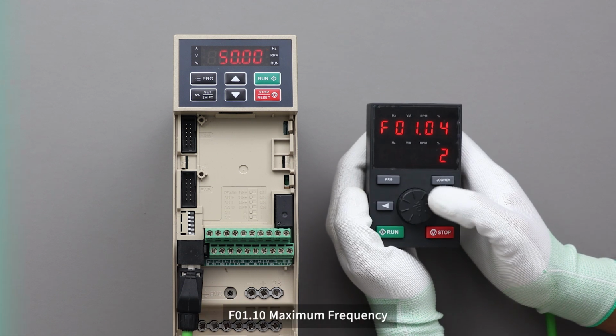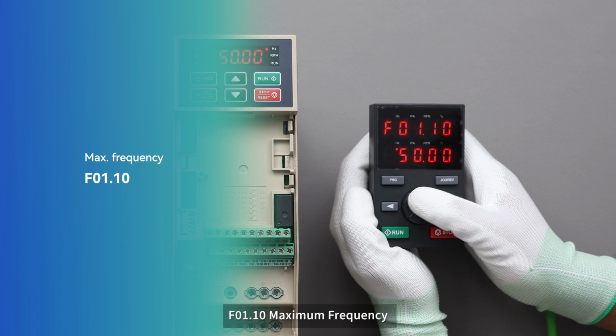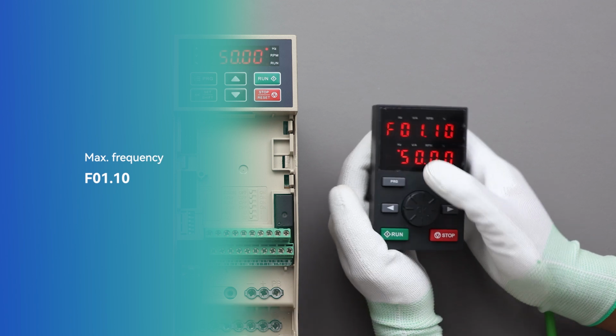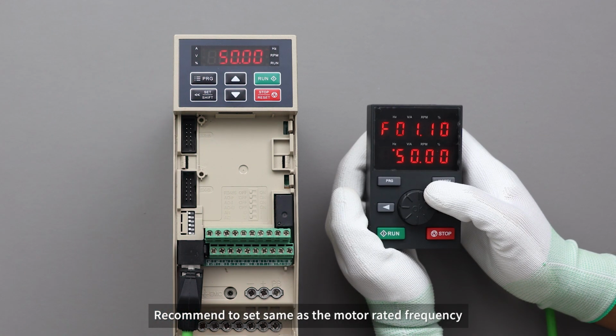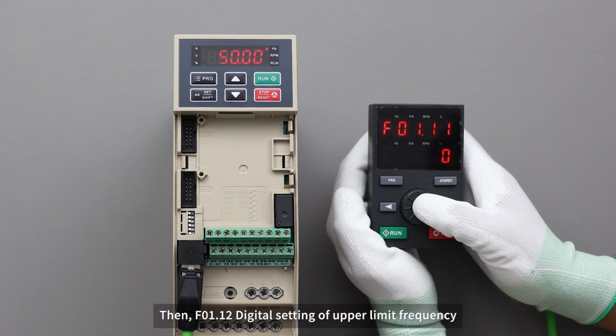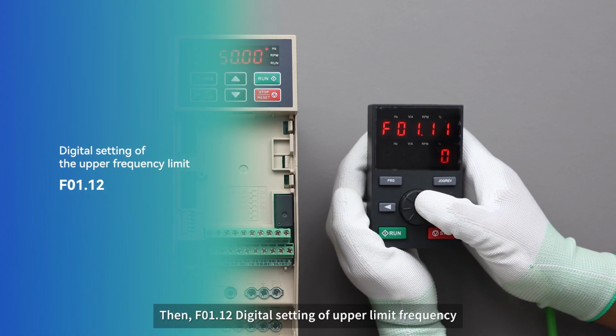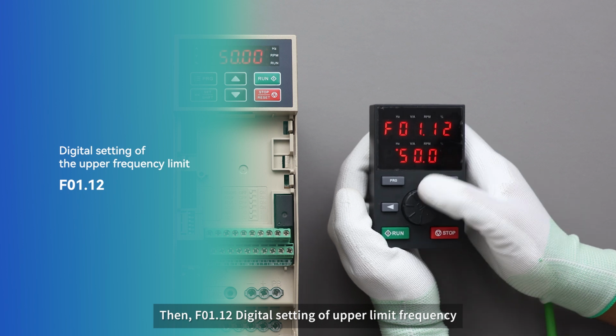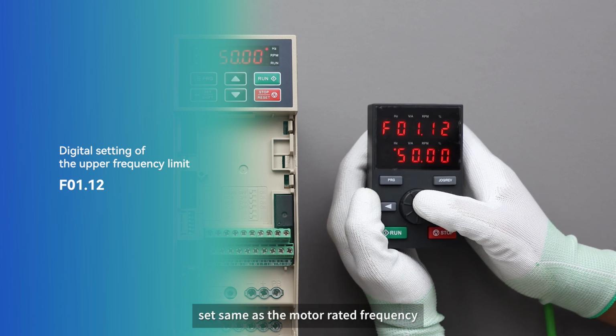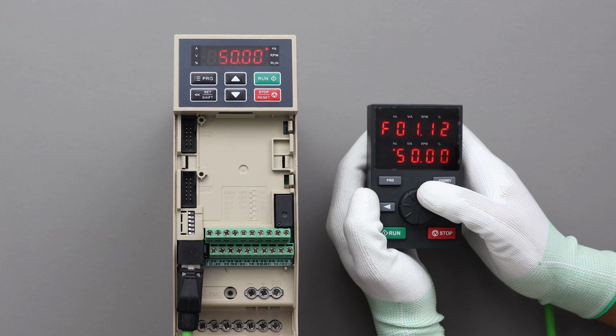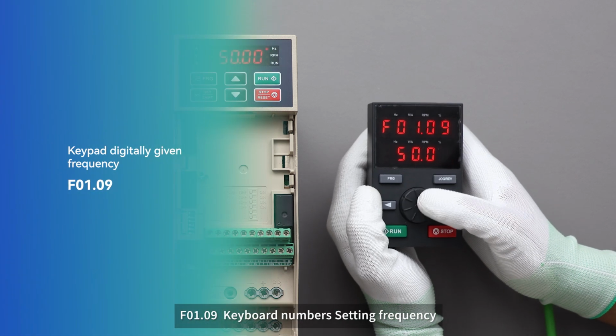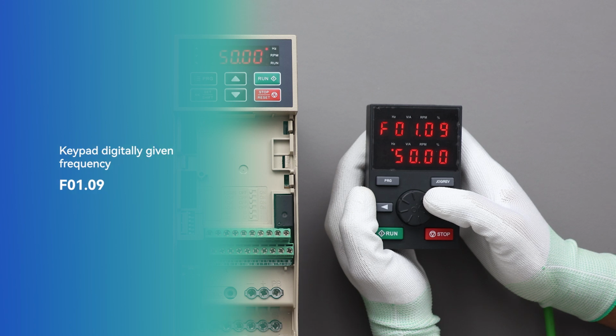First, set F01.10 maximum frequency. Recommend to set same as the motor rated frequency. Then F01.12 digital setting of upper limit frequency, set same as the motor rated frequency. F01.09 keyboard number setting frequency.